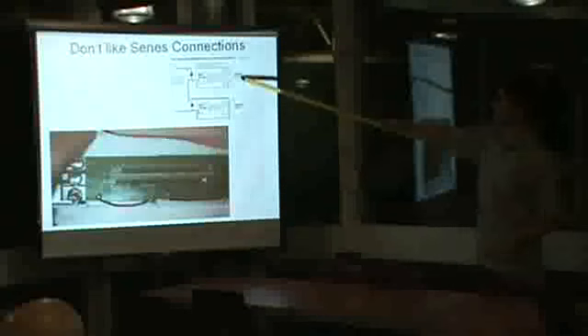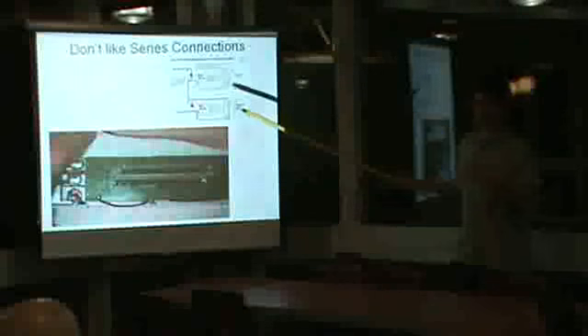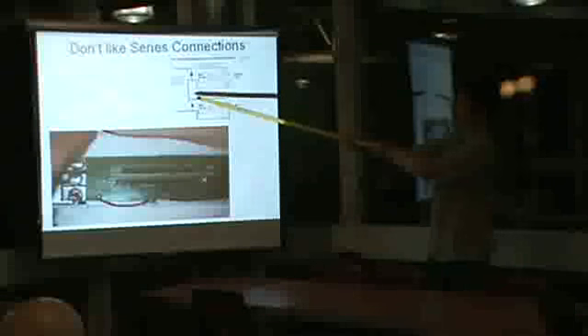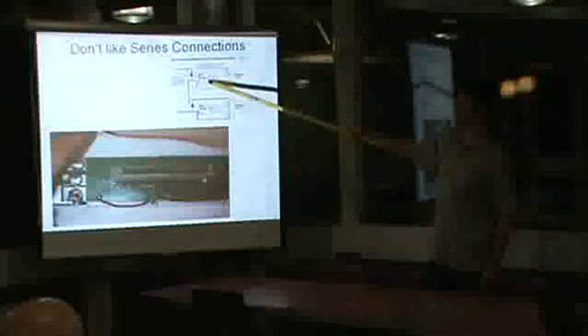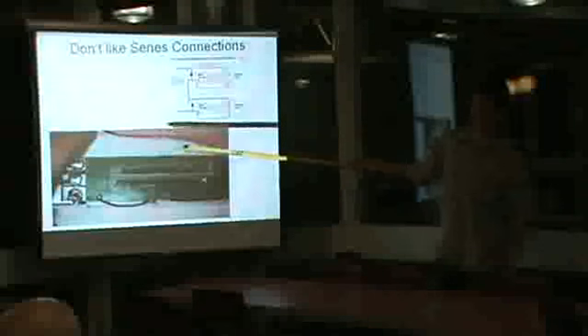I meant to redo this so you could actually see it, but if each battery has its own circuit with a switch that turns it on and off, and you connect two together, one battery will always go flat before the other - even if just seconds apart. You end up with one battery trying to discharge while the other's switch says no more current. But current is already flowing, and there's inductive energy stored in all those wires. So when that switch tries to turn off the battery management circuit, you get a huge voltage spike across the BMS that fries all its chips.